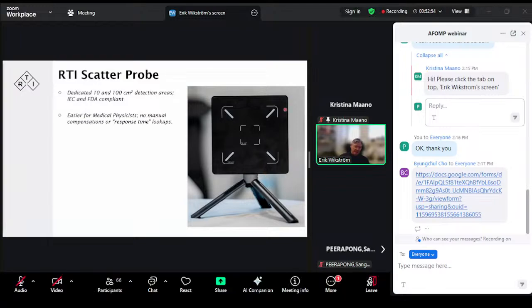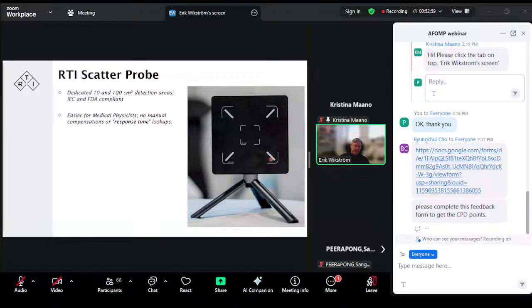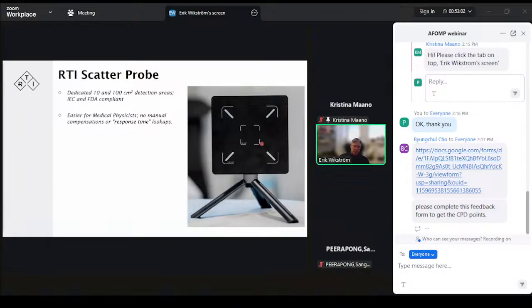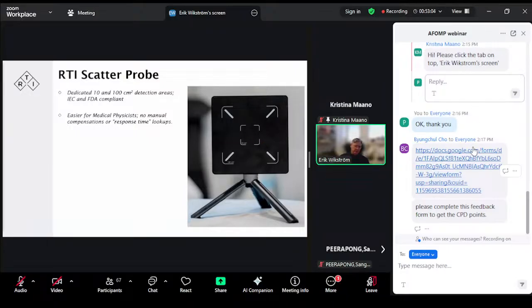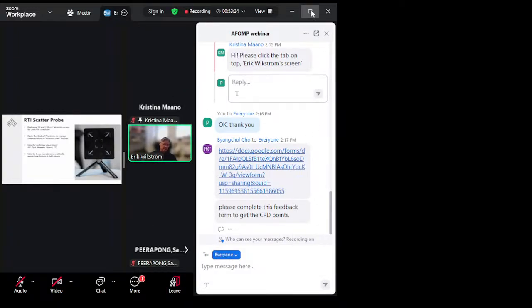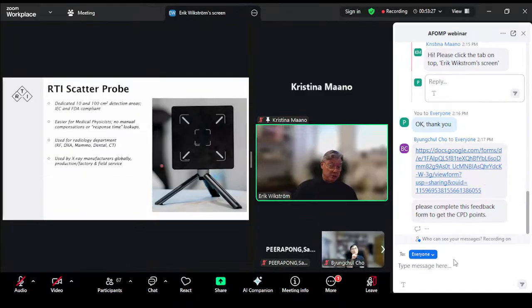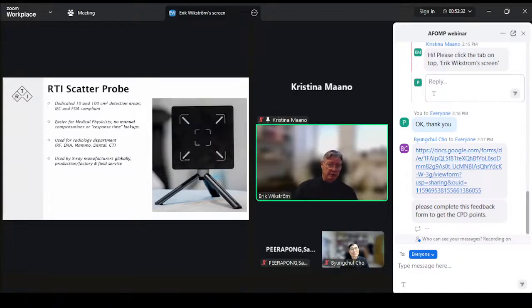Since we also measure the keV, we have a built-in energy response. So there's no need to go into any manuals or tables to look at the compensation tables. The value you get is already compensated. It's used in RF, DEXA, being bone densitometry machines, mammo, dental, and CT. It covers the full range of those applications. So it's used by manufacturers globally to test, both in the production units and for field service.